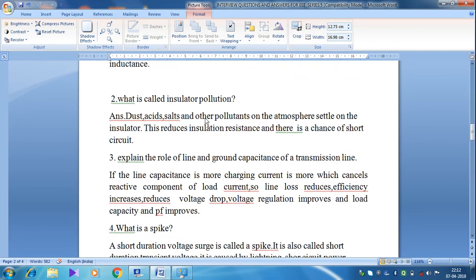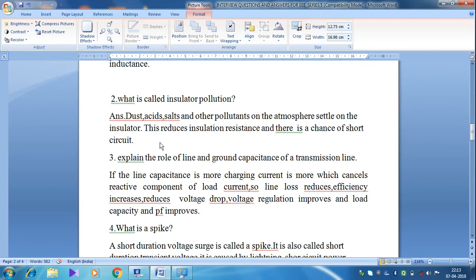The next question is: what is called insulator pollution? Insulator pollution means that dust, acids, salts, and other pollutants in the atmosphere settle on the insulator. This reduces insulation resistance, and there is a chance of a short circuit occurring due to insulator pollution. Therefore, insulator pollution is a very important factor which affects insulation resistance.